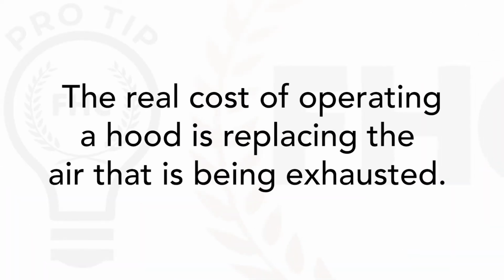One of the fume hood's functions is to exhaust the polluted air outside and away from the building. As this air is exhausted, an equal amount of fresh air has to be supplied to the lab. This supply air has to be conditioned, heated or cooled, and the humidity has to be controlled. The real cost of operating the hood is replacing that air that's being exhausted. When you exhaust less, you need less replacement or supply air, thus saving money.